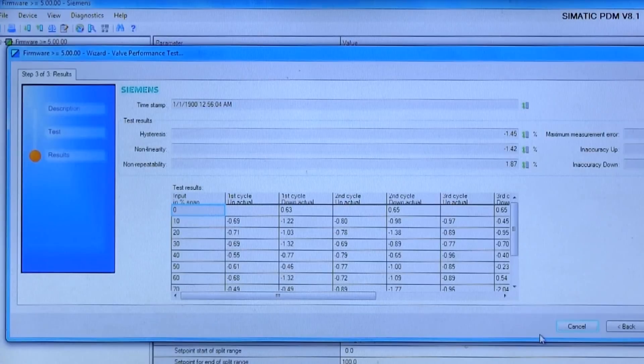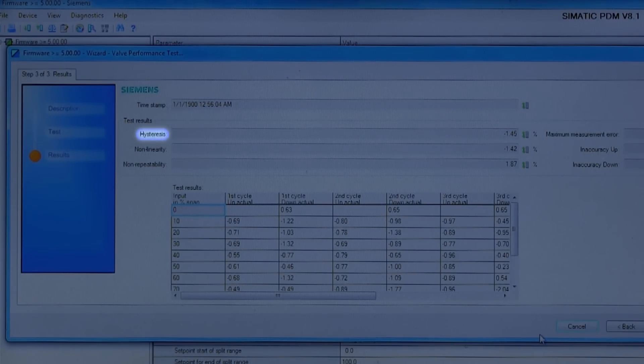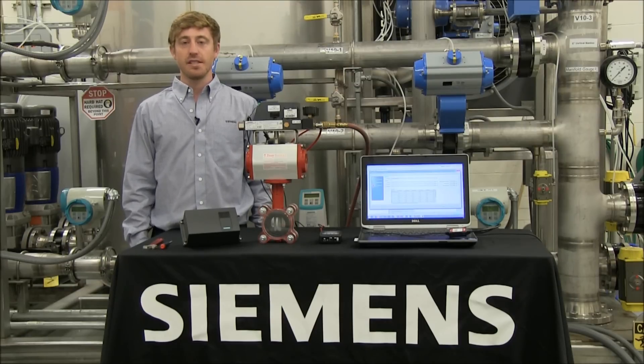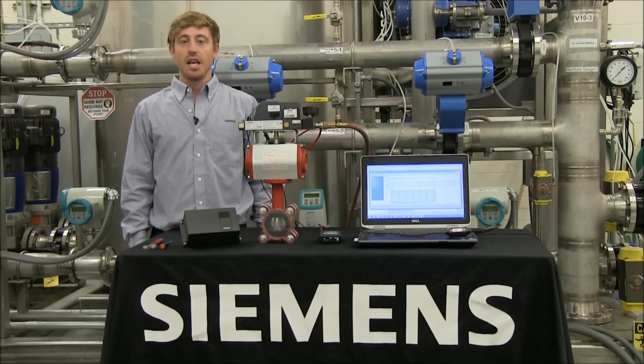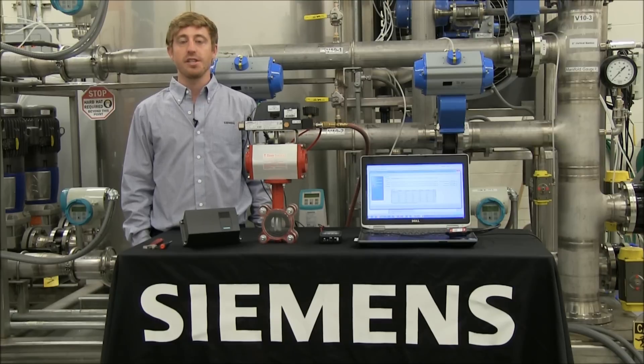Once the test completes, you'll have the following results: hysteresis, non-linearity, and non-repeatability. You can use these data points as a baseline to assess the current status of the valve, as well as a comparison to see how your valve performance has changed over time.